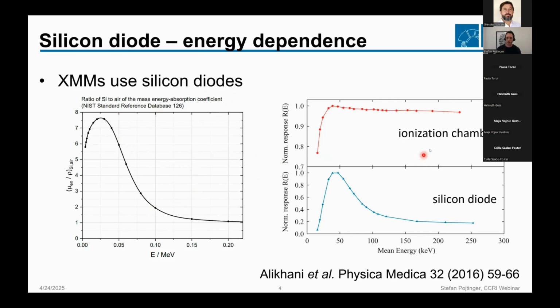On top here, you can see an ionization chamber, and in the energy range of interest, the energy response is more or less flat if you don't go too low. But for the silicon diode, it's exactly that range, that area of the energy, where you have a big change, a big dependence of the response of your silicon diode on the energy. And that makes it so challenging.